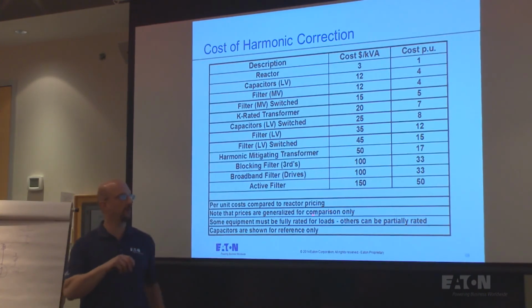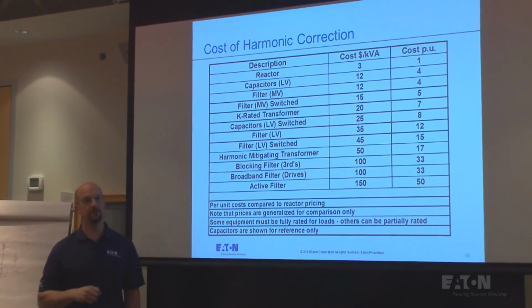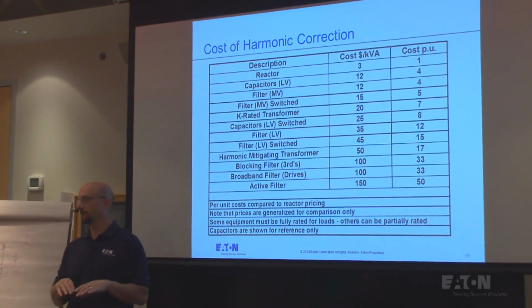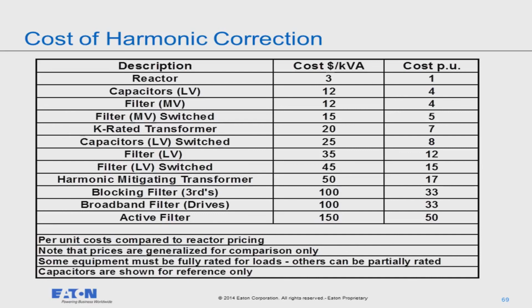Active filters are probably even higher than this, but you know, $150, $200 per kVA or so, and you start to look at, well, that's a fairly expensive thing. So if I can do some of these other things to make the harmonics lower, like phase shifting, and then I tweak the system with my active filter, it's a good design. It's a good way to do it.